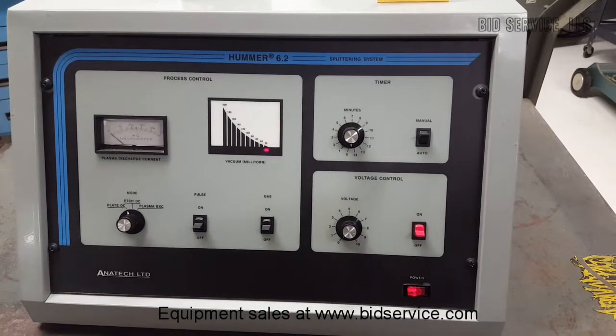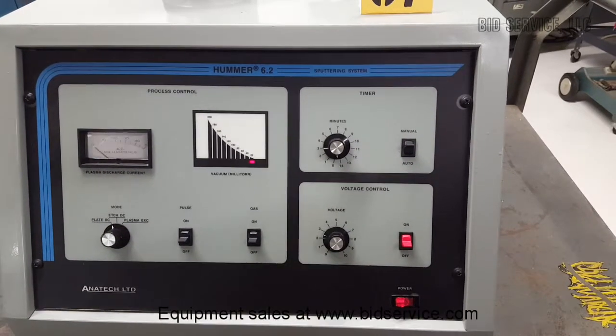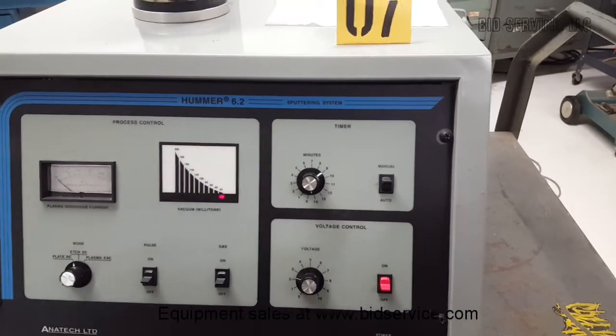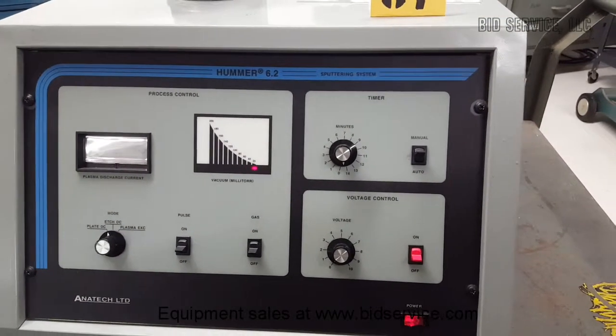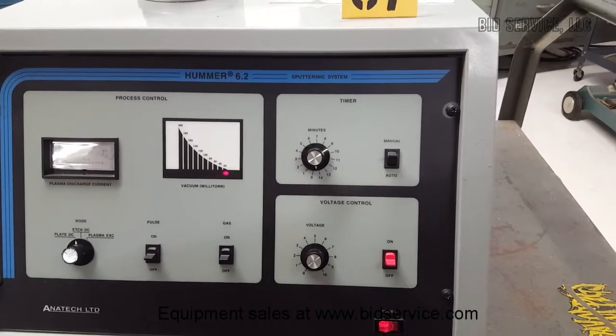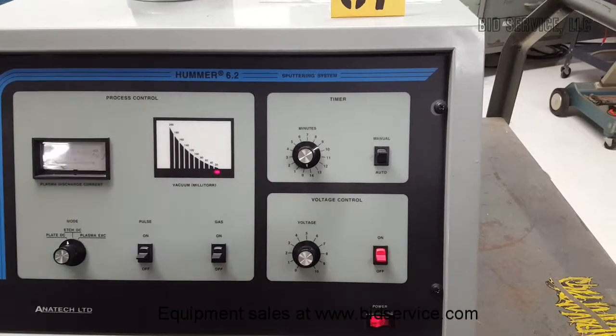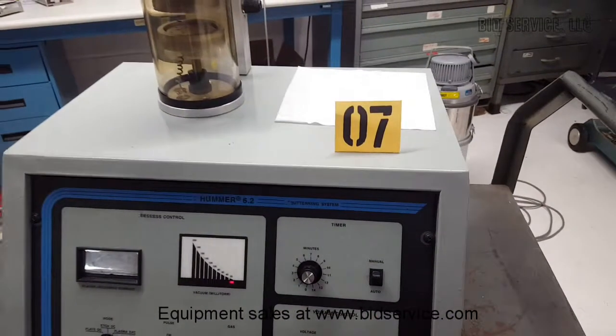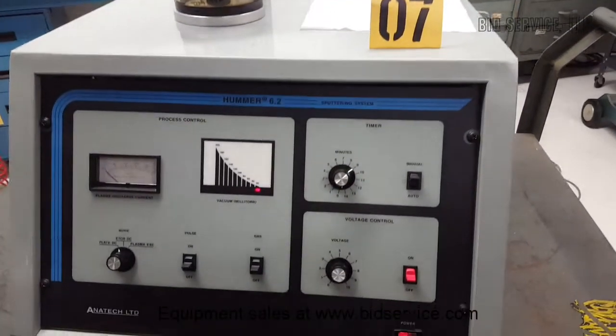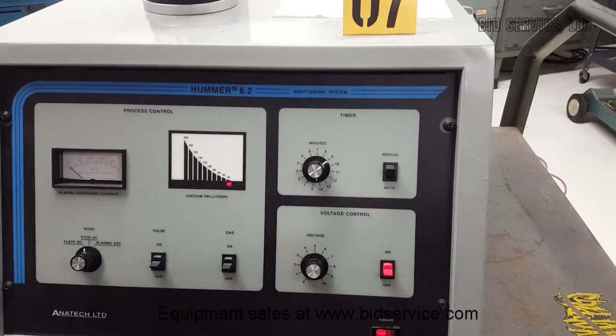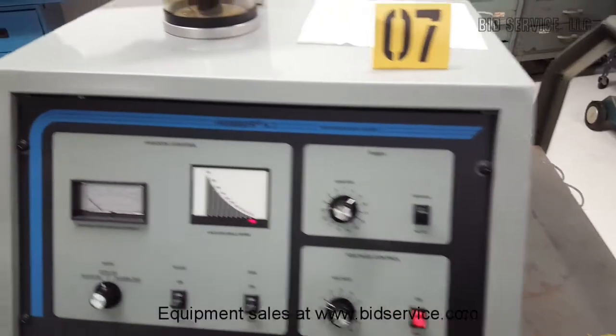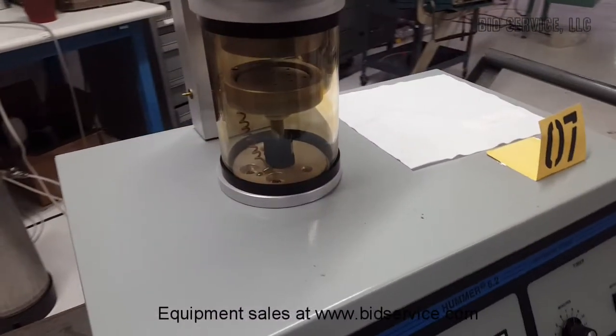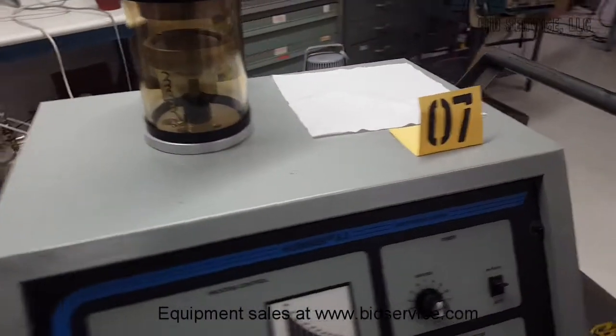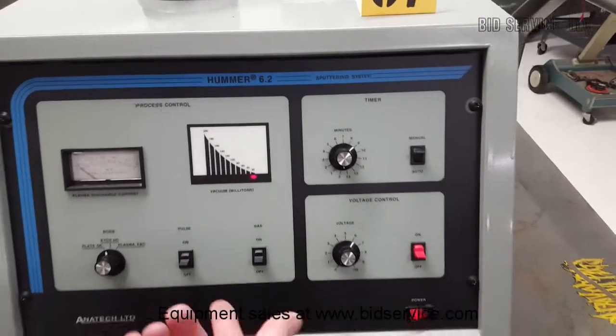So if it's left to run longer, it'll actually go beyond the scale, and the machine will not allow the high voltage to kick in. You'll need a vacuum for the high voltage circuits to be able to kick in as well as the lid being down. There's a lid switch. So once you have your vacuum, you can connect your gas to the port here. Presumably that's argon gas.